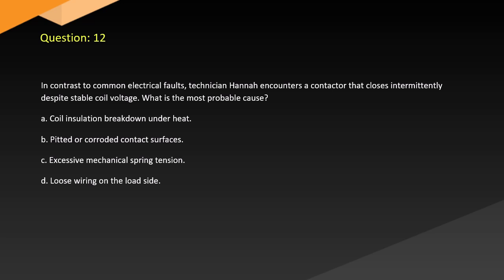Question 12. In contrast to common electrical faults, technician Hannah encounters a contactor that closes intermittently despite stable coil voltage. What is the most probable cause? A. Coil insulation breakdown under heat. B. Pitted or corroded contact surfaces. C. Excessive mechanical spring tension. D. Loose wiring on the load side.